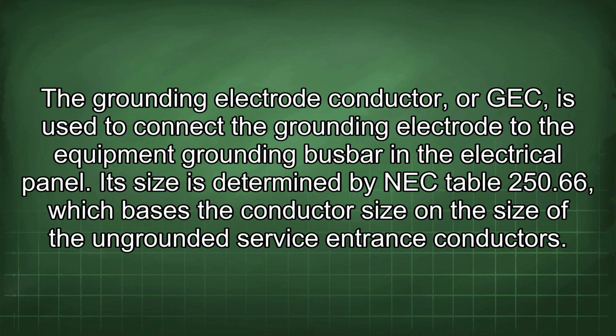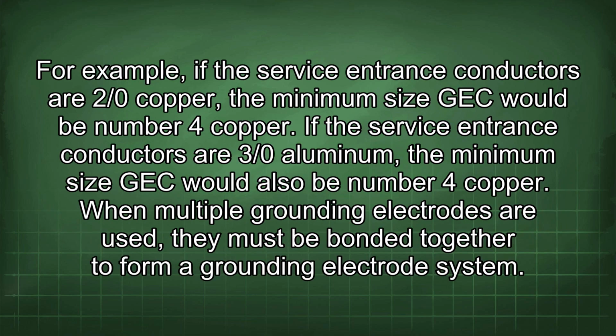The grounding electrode conductor, or GEC, is used to connect the grounding electrode to the equipment grounding busbar in the electrical panel. Its size is determined by NEC Table 250.66, which bases the conductor size on the size of the ungrounded service entrance conductors. For example, if the service entrance conductors are 2/0 copper, the minimum size GEC would be number 4 copper. If the service entrance conductors are 3/0 aluminum, the minimum size GEC would also be number 4 copper.